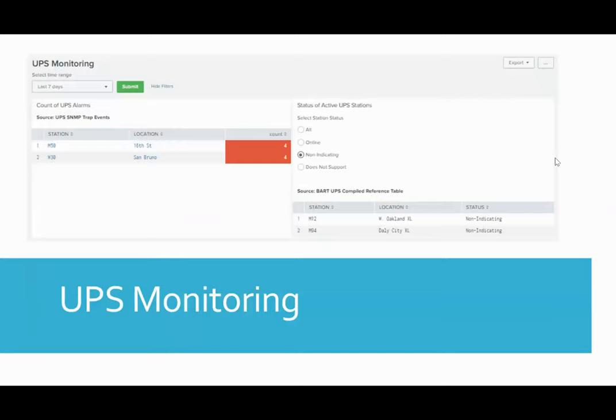Another area with electricity we're focused on is PSPS, when PG&E shuts down power. It's very important for us to know our UPSs are functioning properly. With top-down funding, we're replacing and adding UPSs in the field so that if we lose commercial power, our stations stay operational. This dashboard shows two of our stations where the UPSs are non-indicating, meaning we're not getting information from them, so we need people to go check. In the past we never had a way to know things weren't indicating properly, because older technologies weren't smart enough to have those connections.